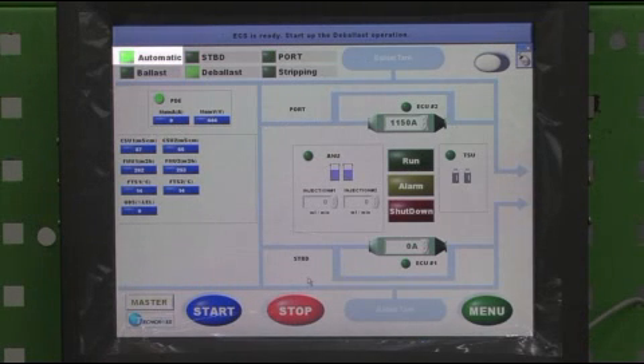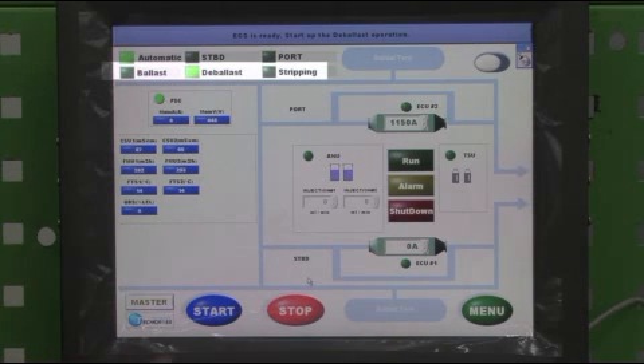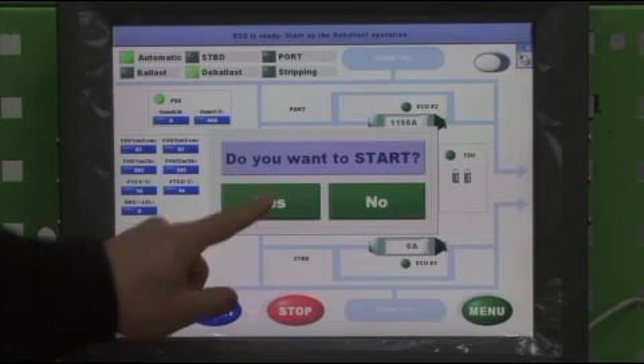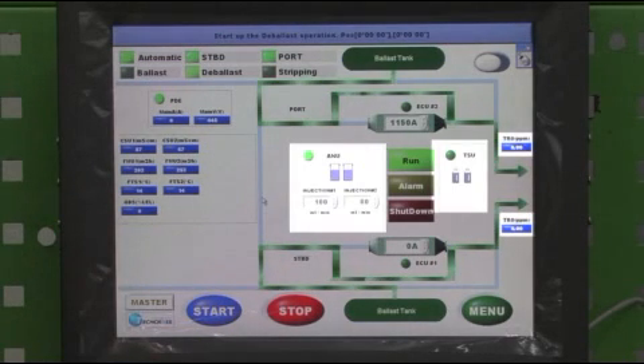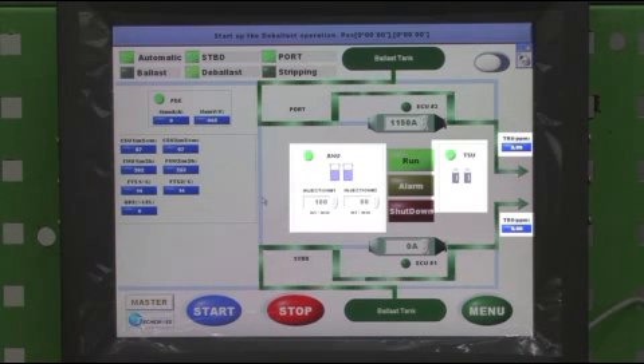Step 1. Make sure that automatic is on. Step 2. Select operation mode after checking related pumps and valves. Please refer to checkpoints before operation. Check the top message and mode display to see if all the deballasting operation requirements are fulfilled. Ensure that the top message says, ECS is ready, and start up the deballast operation. Step 3. Click the Start button on the HMI screen to operate ECS. Step 4. Ensure that the ECU value and TRO value are displayed immediately after operating ECS. Alarm or shutdown should not occur during normal operation.